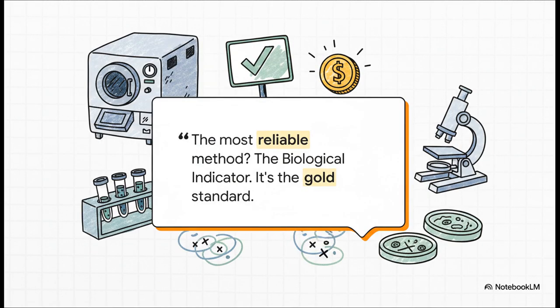And here it is. This is the definitive test. What they do is they place these little vials that contain some of the toughest, most heat-resistant bacterial spores on the planet inside the autoclave along with the instruments. After the cycle is done, they take those vials to a lab and try to get the spores to grow. If nothing grows, that is proof positive that the autoclave killed the absolute hardiest microbes known to science. It's the gold standard for a reason. There's no arguing with it.